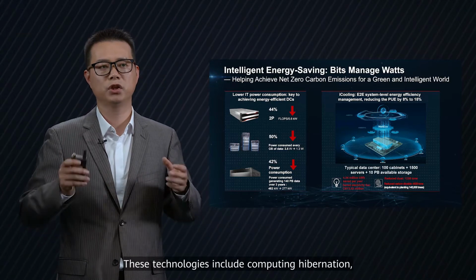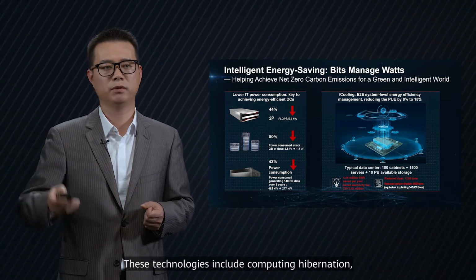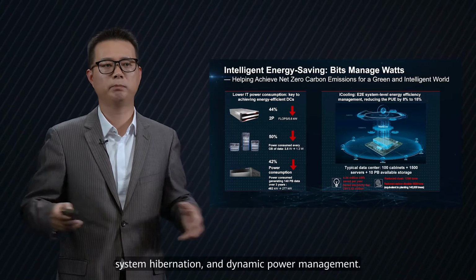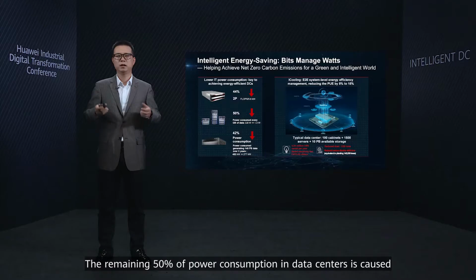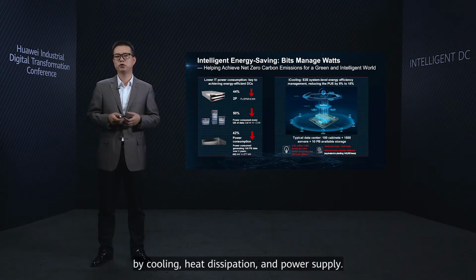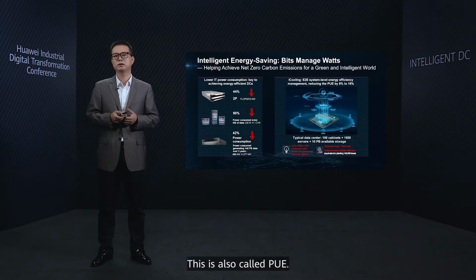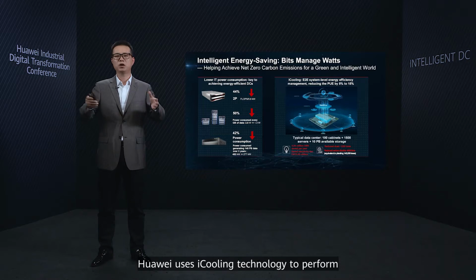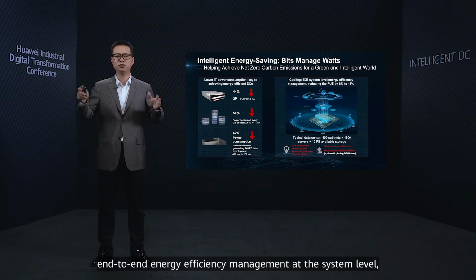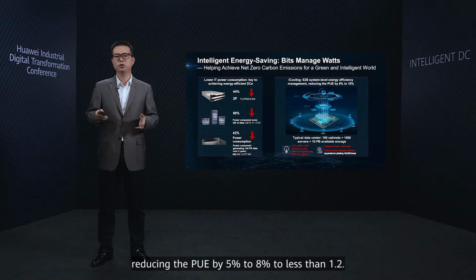These technologies include computing hibernation, system hibernation, and dynamic power management. The remaining 50% of power consumption in the data center is caused by cooling, heat dissipation, and power supply, also called PUE. Huawei uses iCooling technology to perform end-to-end energy efficiency management at the system level, reducing the PUE by 5 to 8% to less than 1.2.